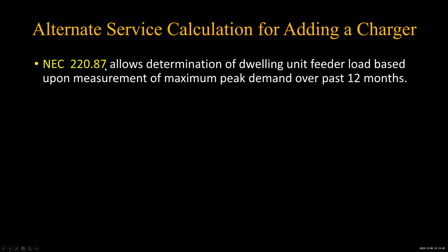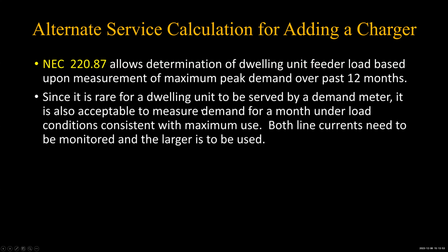Here's an alternative service. Here's your 220.87, okay? And it says you can do that, but it doesn't happen very often. So you can also measure for a month if you know this is a month when you have your highest bill. If you put recording ammeters on L1 and L2 and measure both currents for a month, then you take the larger one and multiply by 125%, and that's your new load calculation if you want to wait a month to get it, and if you got the recording ammeter. So that's what you can do at 220.87 in a residential situation.